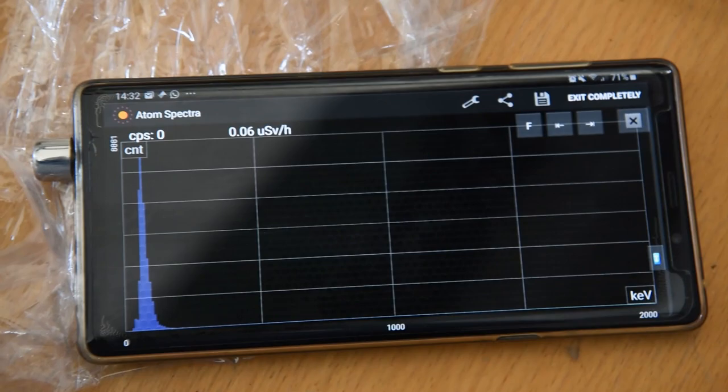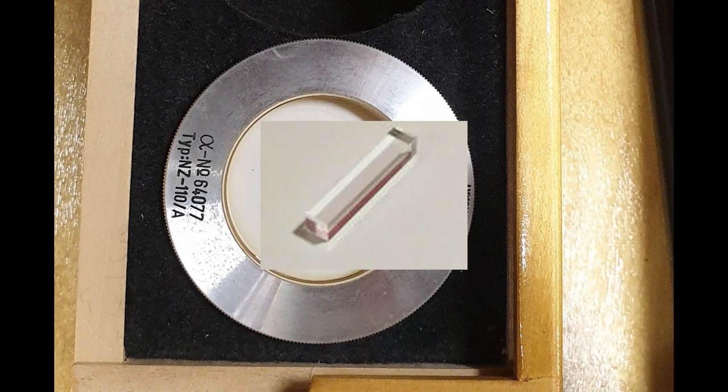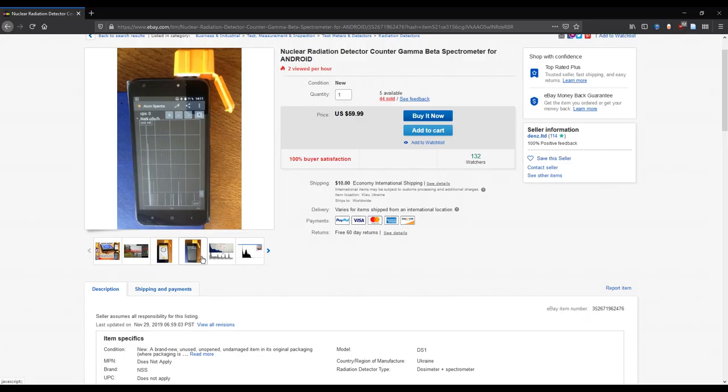The amount of energy deposited mostly depends on the size and density of the crystal. Both are low because we can see the detector is small and the detector is made of plastic, which has a very low density. The better scintillators are made of crystals like sodium iodide or cesium iodide or maybe something even denser.